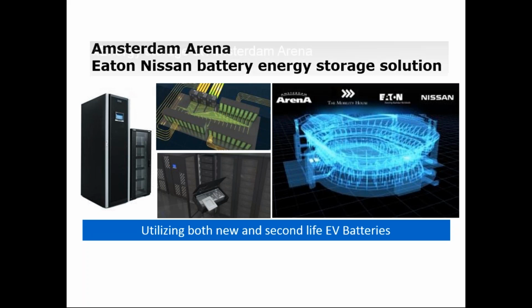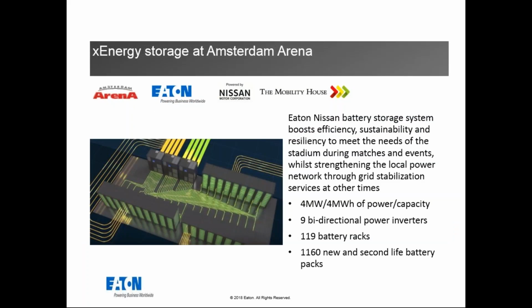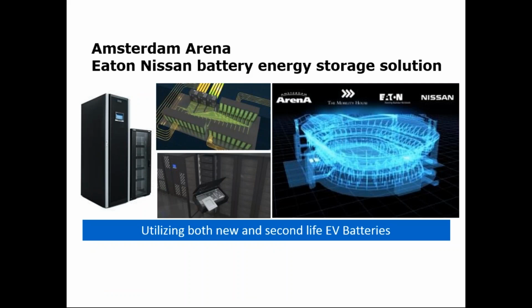The second element of the system is the larger unit on the left-hand side - sorry, if we can go back to that slide - and this is what we call the power inverter. This is the equipment that converts power from the battery and puts it back onto the power distribution system of the building. It actually works bi-directionally, so it can take power from the network to charge the batteries, or take power out of the batteries and put it back onto the network to power the building. In simple terms, those are the two basic building blocks of a battery energy storage system.